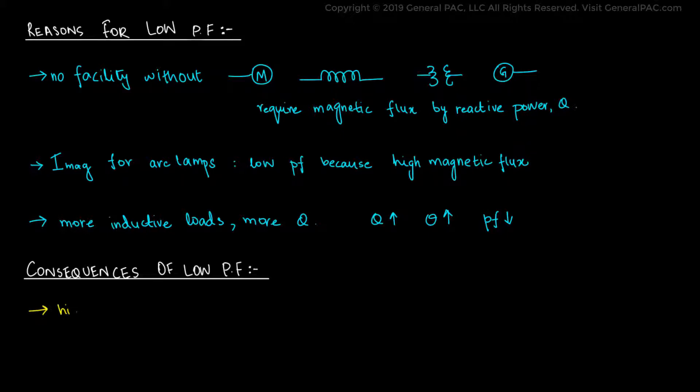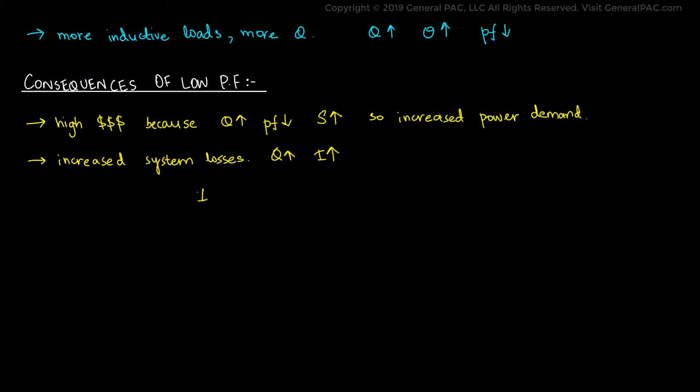The first and foremost important reason is high utility cost. This is because a higher reactive power and a lower power factor causes an increase in overall apparent power drawn by the system and subsequently increasing the power demand of the facility. Another issue caused by low power factor is an increase in the system losses. A higher reactive power requirement draws more current and the square of the current is directly proportional to the line losses.